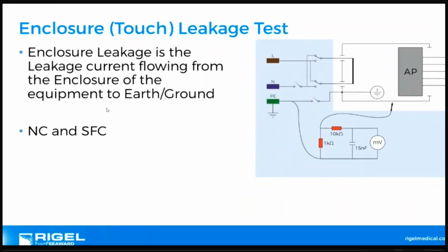Touch current, as I explained in the previous, the earth bond. If I've got my functional current, 100 milliamps flowing, but there's only 99, and I've got some kind of stray capacitance or dielectric resistance, then the fault current will flow through the device to the chassis. And if I'm touching that, because the earth's open here, then this fault current has nowhere to go. So I'm measuring it through the device with the safety analyzer in that scenario. But if I was touching this and I happen to be earthed, I'm going to get that electric shock.